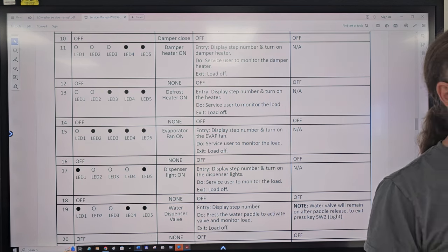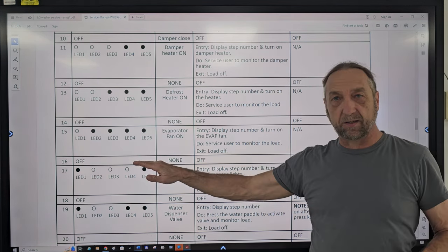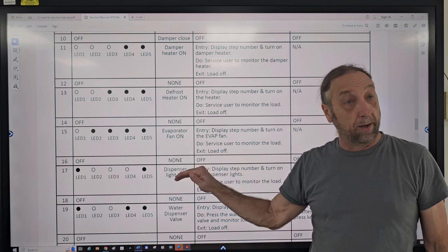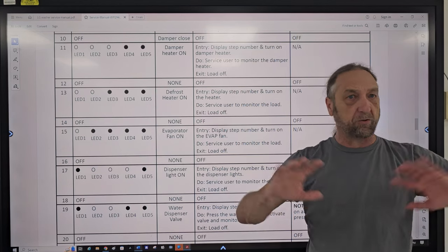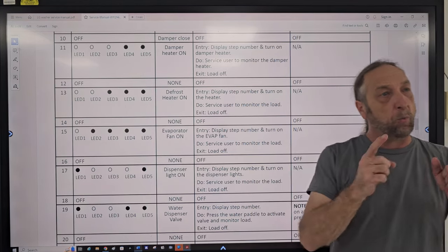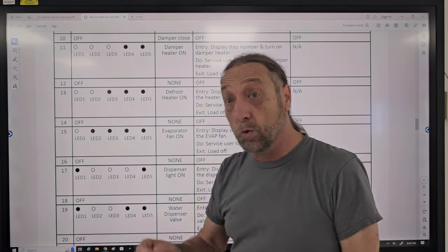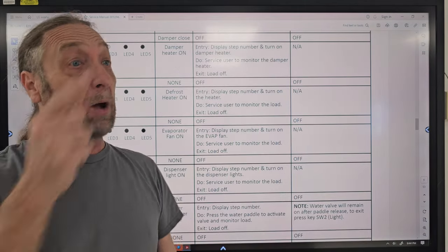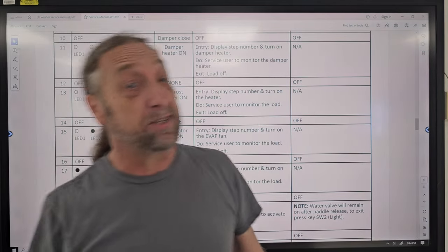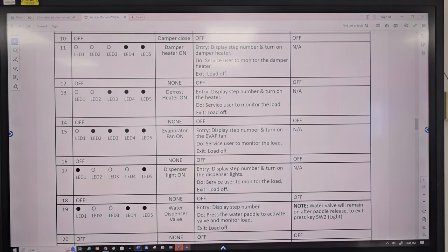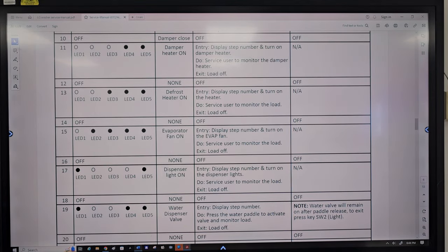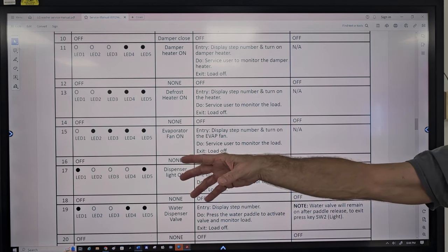But in diagnostics, when you go to that specific step, the only thing running is the fan motor - no compressor, no other fans, nothing. When you're in that step, you know the board is saying, hey, I want this part to run, and it should be sending power to that part. So you go into diagnostics just to check that power.